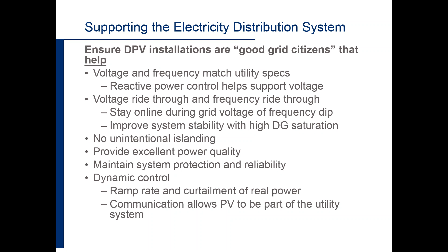This incorporates safety and equipment failure issues, the ability to provide excellent power quality, and that includes harmonics, and making sure the voltage is matched to the utility, system protection, making sure that the fuses along the lines and the circuit breakers at the substations are coordinated, and they also can add to synchronization, protection against some of the islanding, grounding, have disconnect devices, protective relays. There's a lot of ways that these DPV systems can actually balance the grid more than harm the grid. To do that, really involves having an appropriate interconnection process.